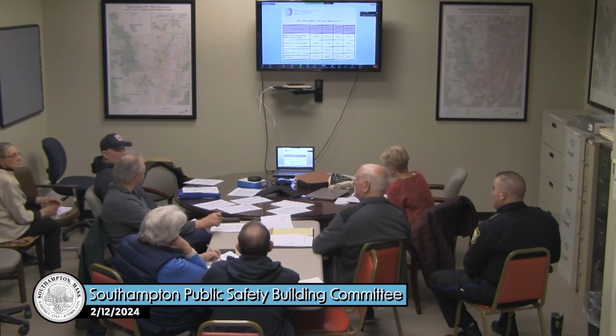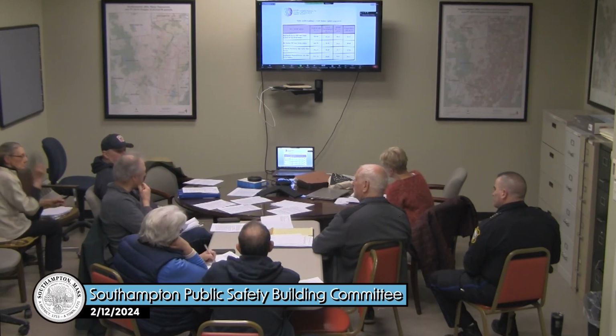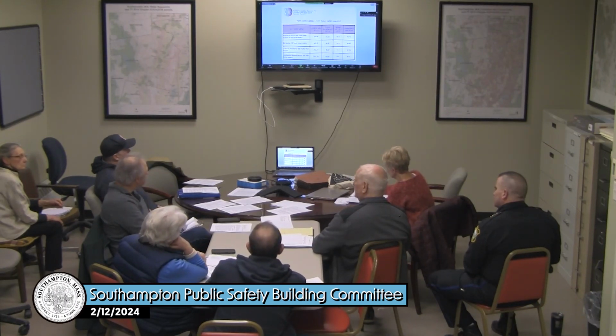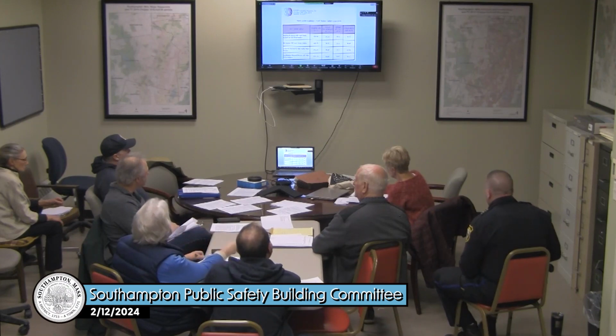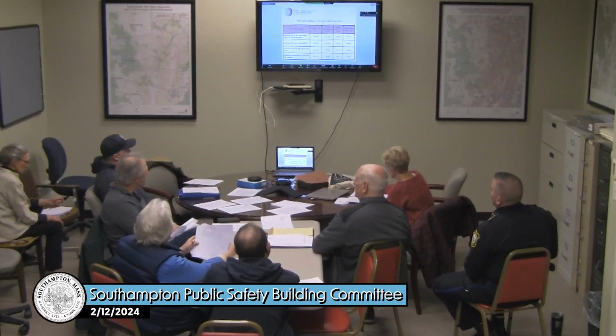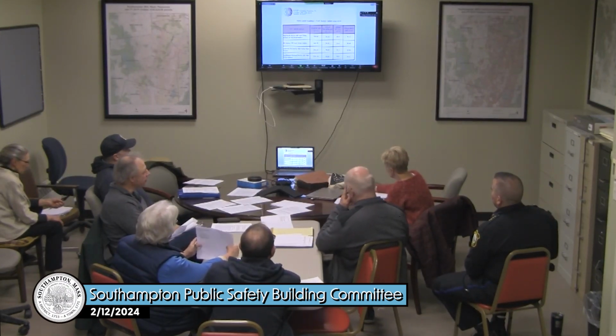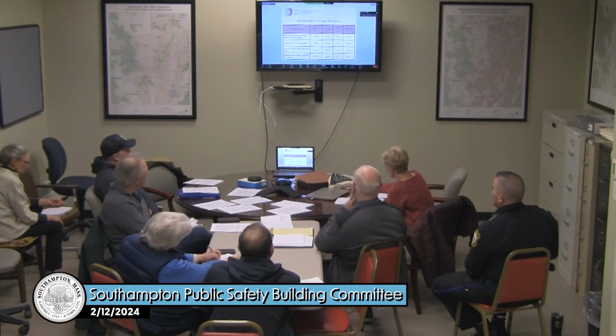To get back to the PV concept, if we opt not to do that initially, would the roof structure be inherently able to sustain that weight if we decide to do it at a future date? It's actually a code requirement to provide a certain percentage of the roof to support future PV. So from an electrical standpoint, we need to provide the infrastructure and switchgear sized to accommodate that, and also the roof to support it where it makes sense.